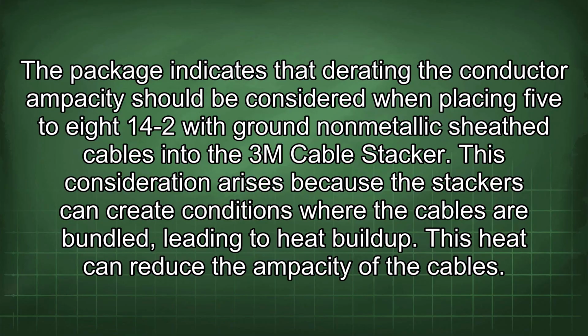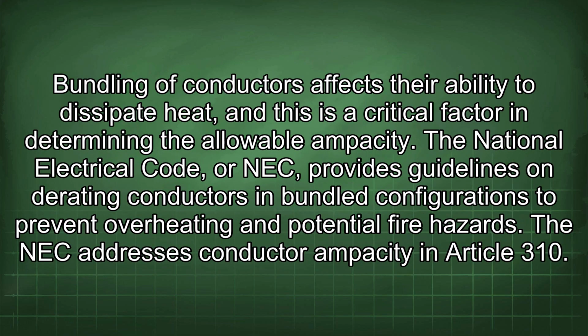The package indicates that derating the conductor ampacity should be considered when placing 5 to 8 14-2 with ground non-metallic sheathed cables into the 3M cable stacker. This consideration arises because the stackers can create conditions where the cables are bundled, leading to heat buildup. This heat can reduce the ampacity of the cables. Bundling of conductors affects their ability to dissipate heat, and this is a critical factor in determining the allowable ampacity.